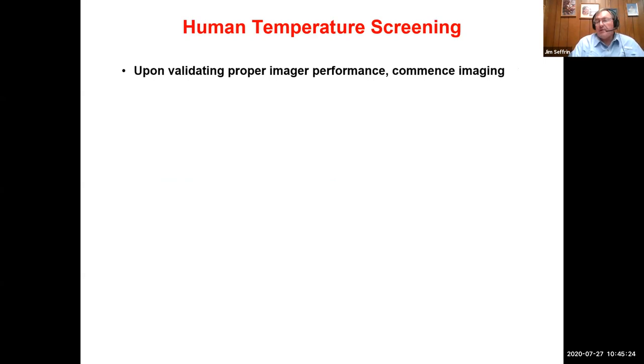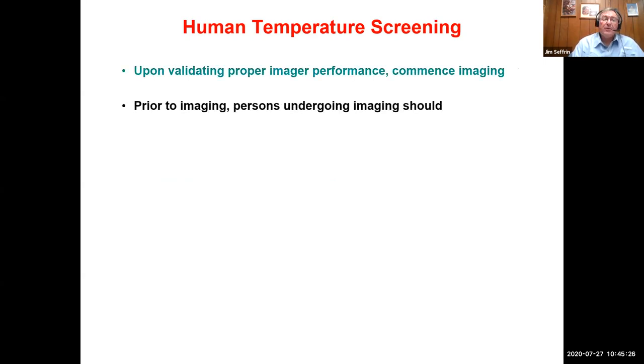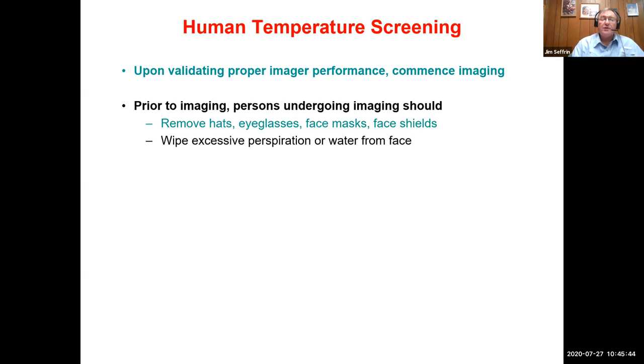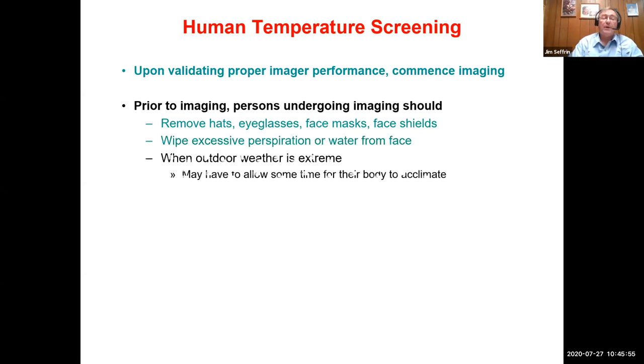Once you've validated proper imager performance, you then commence imaging of your subject persons. Prior to imaging, persons undergoing imaging should be properly prepared. They should remove their hat, eyeglasses, face masks, and or any face shield. This is just temporary, but the imager won't see through eyeglasses, so they need to remove everything so we have a clear view of their face. They should also wipe any excessive perspiration or water from their face. If they're coming in from outdoors and it's been snowing and the snow is melting on their face, or they've come in from the rain, you've got to have a dry face in order to do this properly.